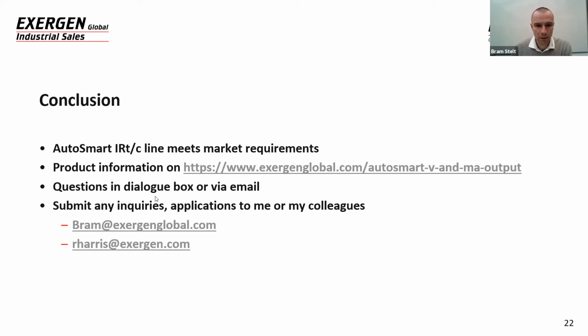Let's see if we have some other applications or other questions. I'm just scrolling through the questions if I see any ones that are double maybe. Does this solution work with any controller, any PID? Well, basically, any readout device, controller, data logger that has an analog output of 0 to 20 milliamp, 4 to 20 milliamp, or 0 to 10 volt, 0 to 5 volt, the ones that I mentioned, you can connect it.